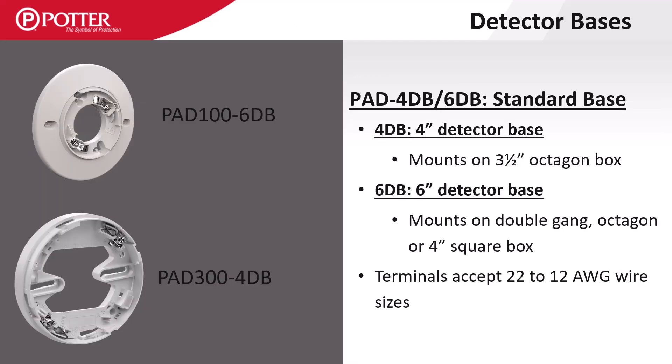The PAD-4DB and 6DB are standard 4 and 6 inch detector bases. The 4 inch base mounts on a 3 and a half inch octagon box only, while the 6 inch can mount on several different boxes.